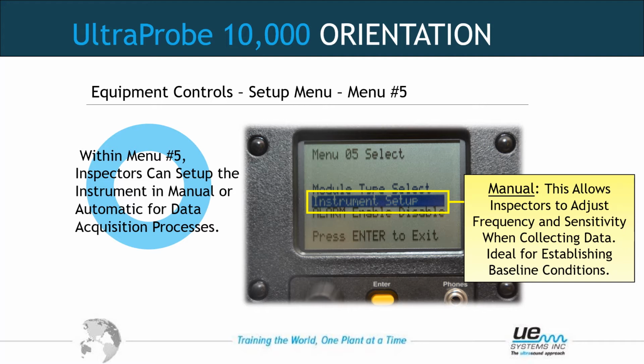In manual, we would set it up for record 1, frequency of 30, sensitivity of 25, store the information. When we go to record 2, it is still at 30 kilohertz and the sensitivity at 25, somewhere near where we were last. Is much better than the default values. So manual for baselining, automatic for any other time you run the route. Once everything is baselined, you have all your routes up and running, the gun should stay in automatic. The only trouble is when we are having some routes run and some routes being baselined, we have to remember to swap between the two, manual or automatic in instrument setup.